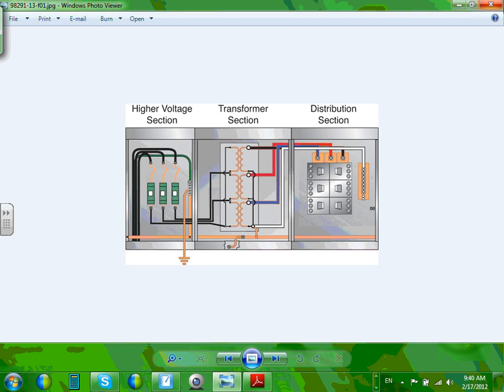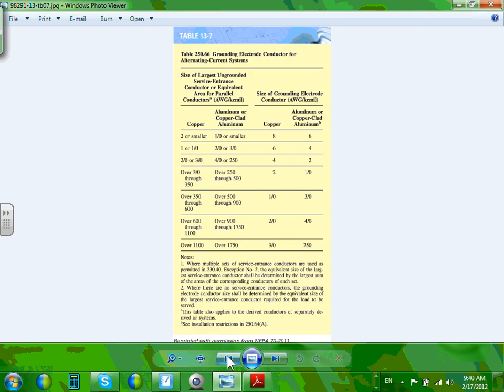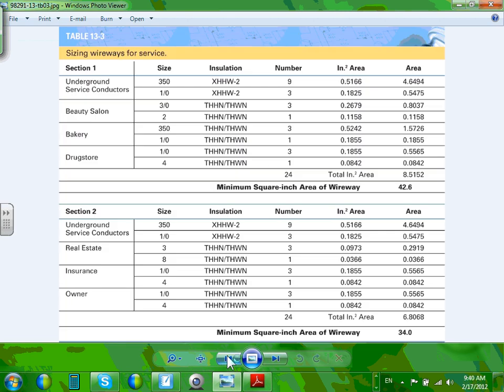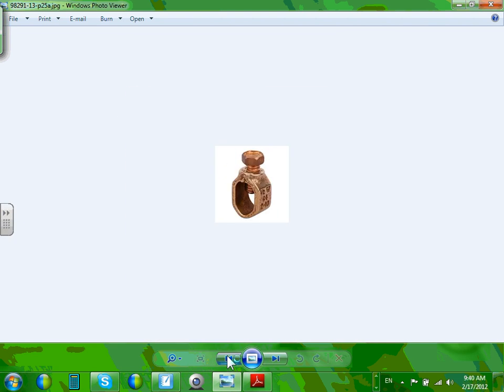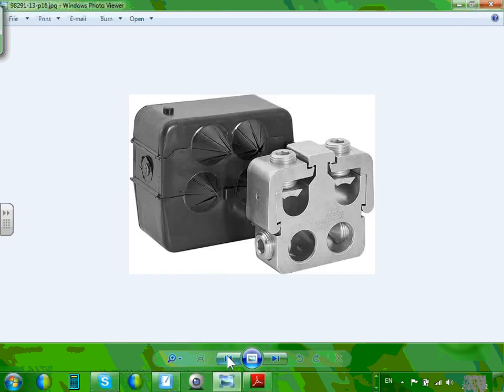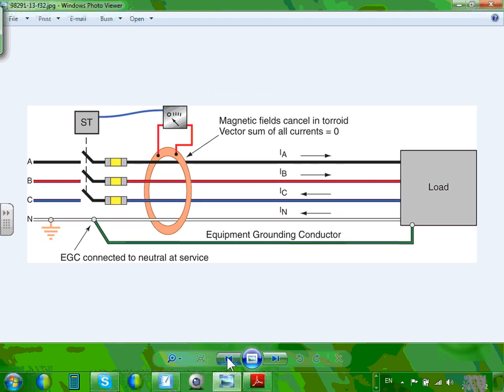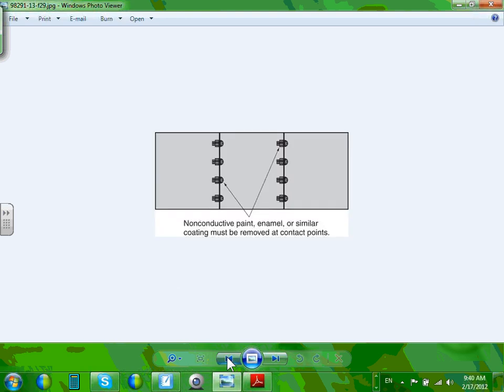Please, will you explain the main difference between the main bonding jumper and the system bonding jumper? Okay, let's go back. Main bonding jumper, system. Well, I can explain it in two words. The main is at the service. The system is at the transformer that you own and operate down in your building. Okay, there's an example here. They really do the same thing. They actually look alike, and we size them exactly the same.